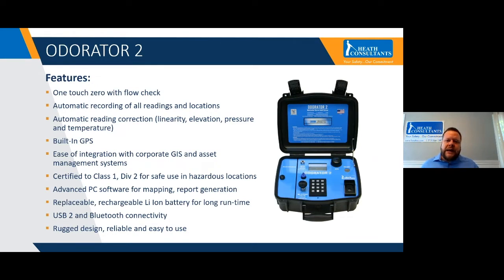Now we have the ability to record all locations and readings that are being tested. Also, the correction is now all taking place automatically within the Odorator 2. So no more correction charts, no more correlation, no more customization for each of the environmental characteristics you might face in the field. Whether it be elevation, pressure, or temperature, these are all corrected for within the Odorator 2.